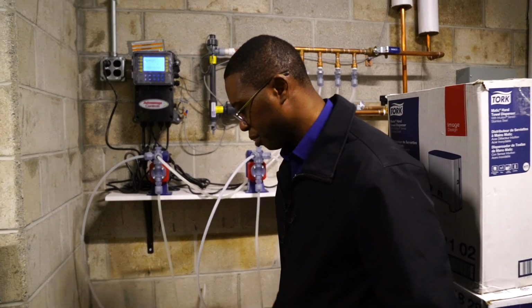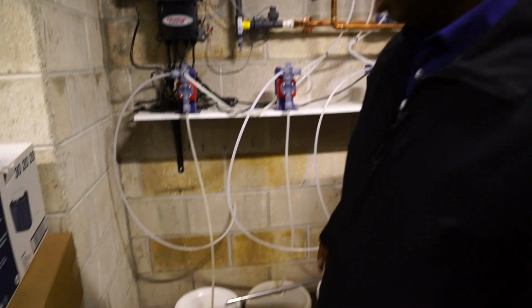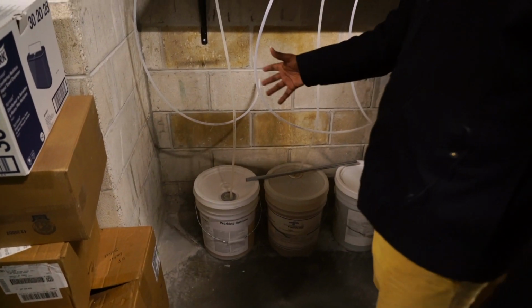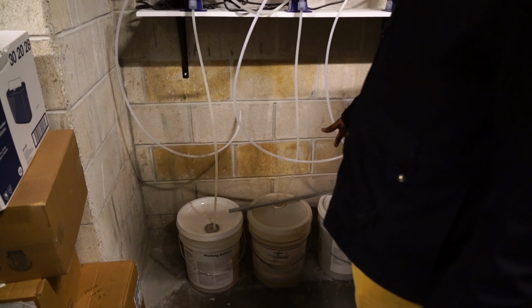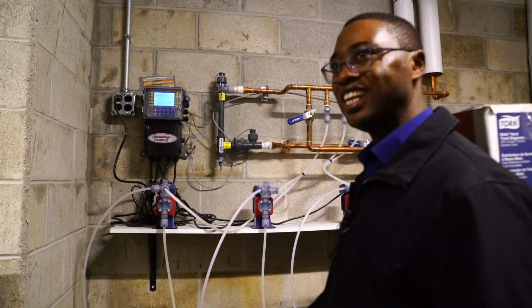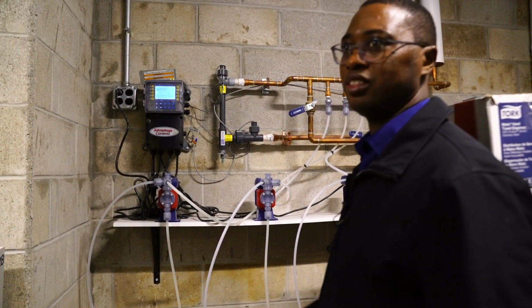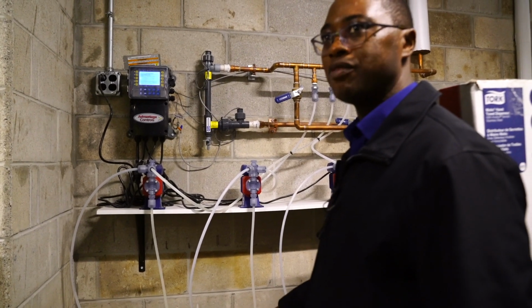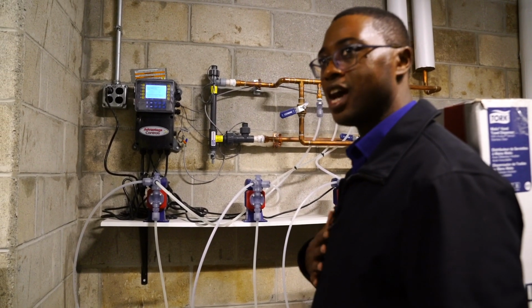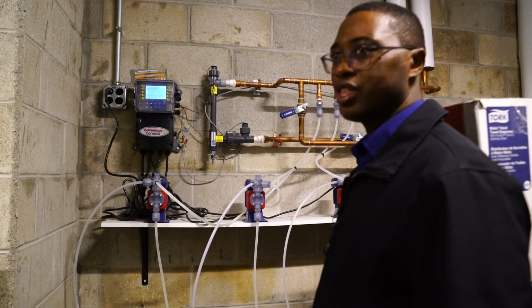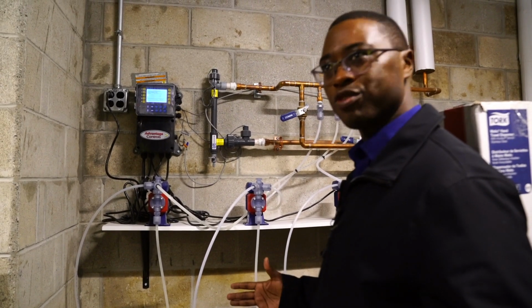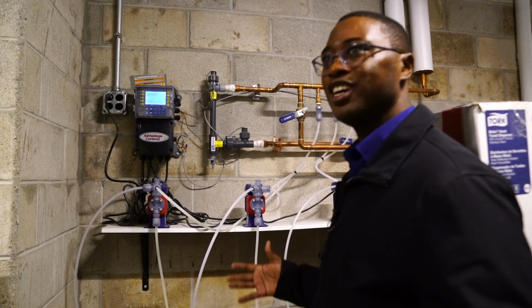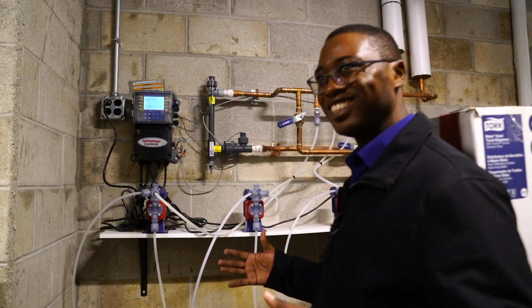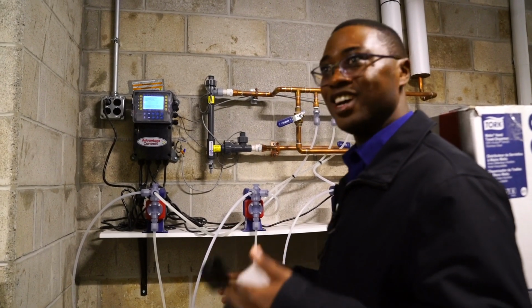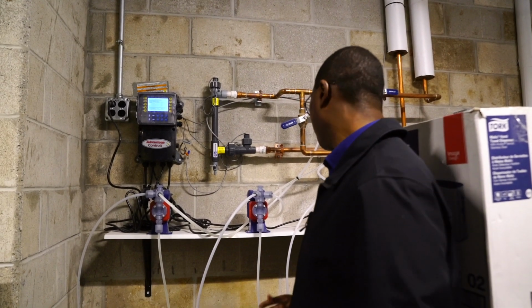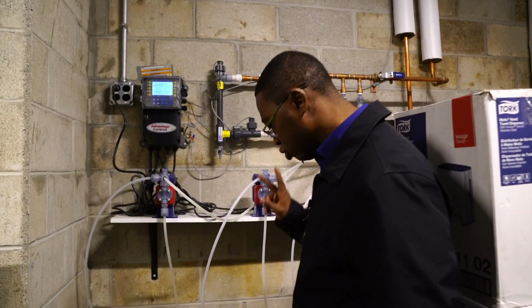Now, if I can move this, I'm also going to have my guys change this. I don't think you should operate in 5-gallon pails. You should operate in at least 15 to 30-gallon drums. So I'll have that changed. I'll put in 30 gallons so that in a space of 30 days you have the chemicals you need. With 5 gallons and a delivery that comes once a month, you could run short of chemicals. You have 3 pumps, and you have 2 biocides.